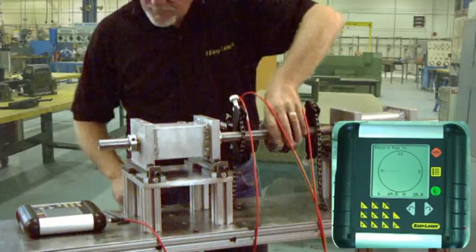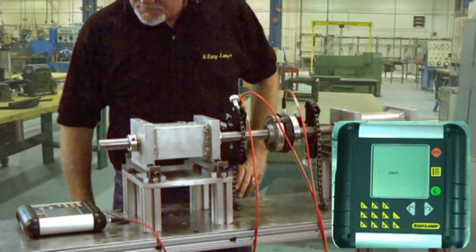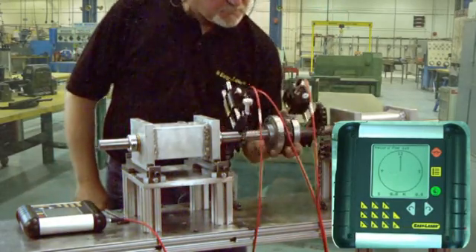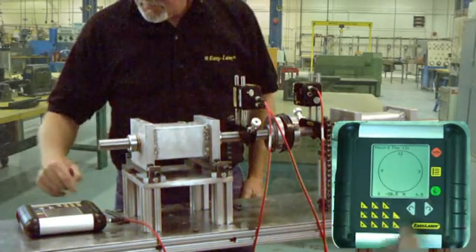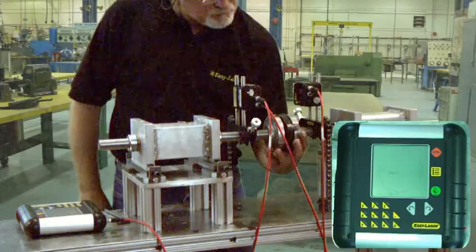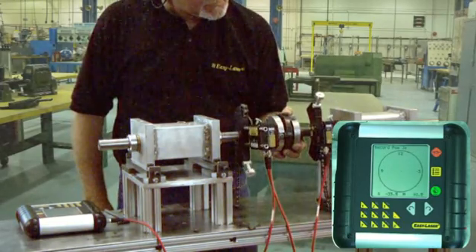We position the units with the spirit levels and press enter to record the measurement. Next the display prompts us to record at the 12 o'clock position. Finally onto the 3 o'clock using the spirit level to position the heads each time.